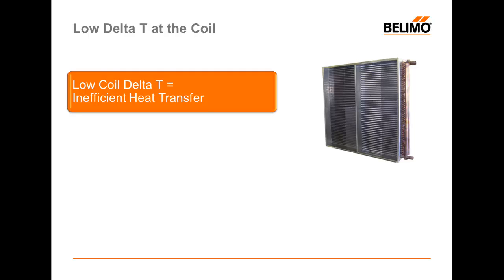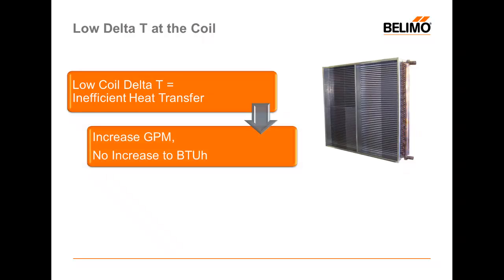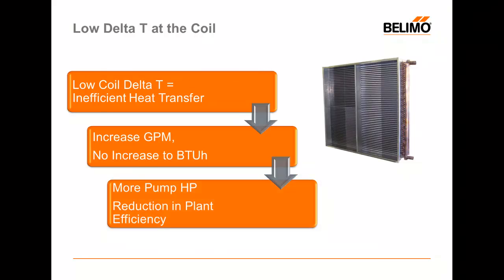Low Delta-T is inefficient for several reasons. Since we're not making the water any warmer, it means we haven't transferred that heat into the space. In order to achieve this type of low Delta-T, it means we have to increase our GPM — we're flowing water faster and not increasing any BTU output. When we do this, we obviously incur more pumping costs from pumping more water, and we reduce our overall plant efficiency.